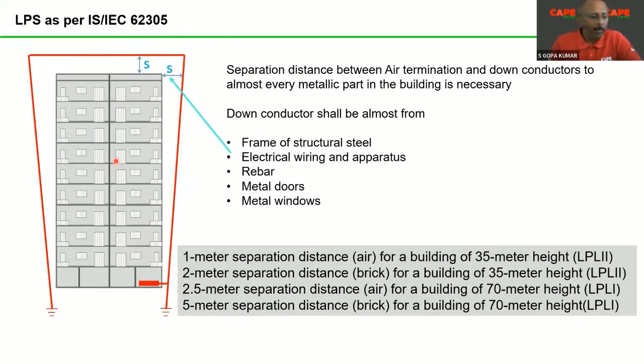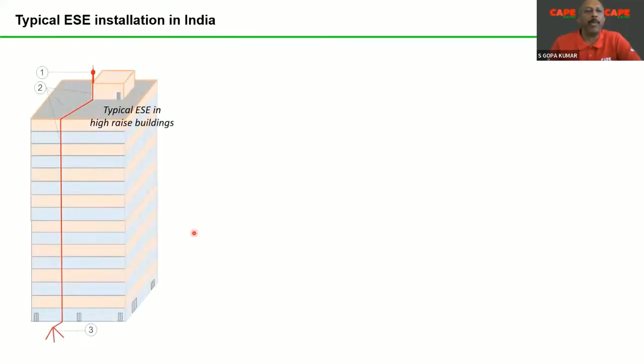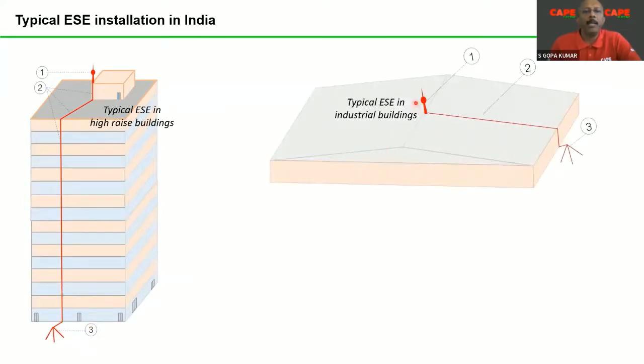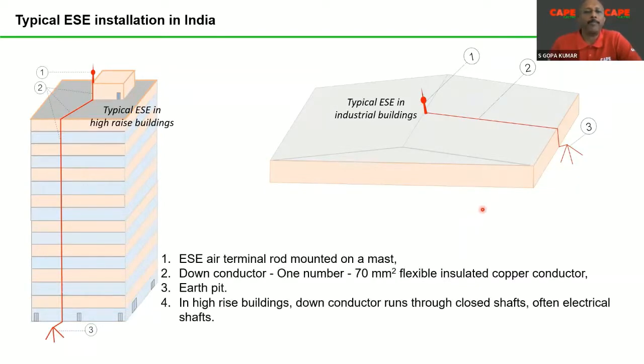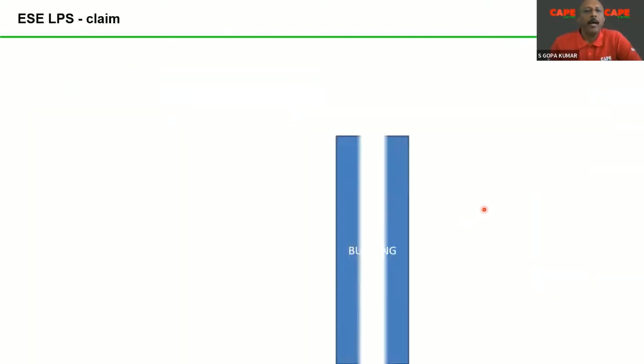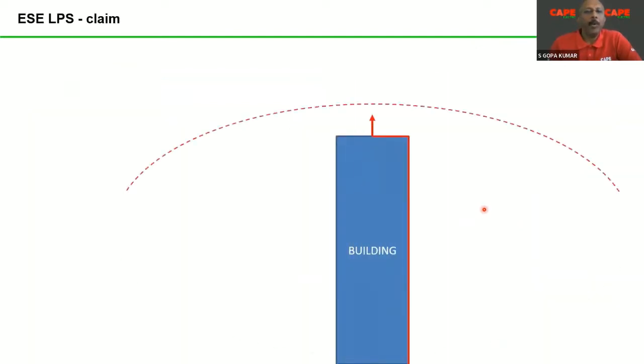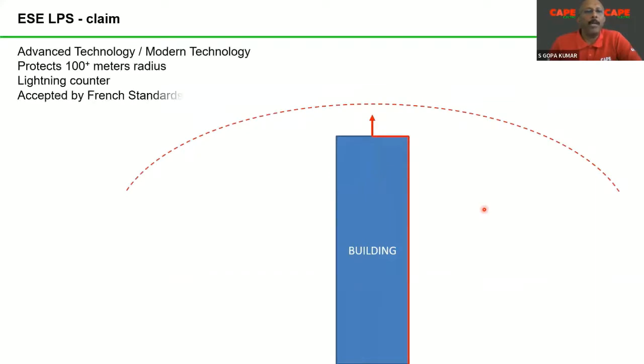The second claim: a lot of high-rise buildings in India are using a non-standard air termination called the early streamer emission system. All of you know it very well. One rod, one down conductor and one earth electrode. In large industrial buildings, again, one rod, one down conductor and one earth electrode. What is this down conductor? In 90% of the cases, it is a 70 square millimeter insulated copper wire. What is the claim? These manufacturers claim that one rod protects 100 meters, and finally the claim is that it is as per the French standard, NFC 17102.